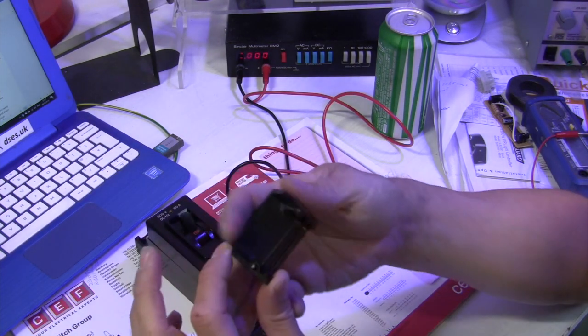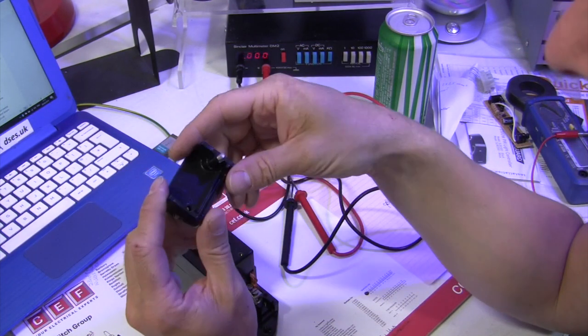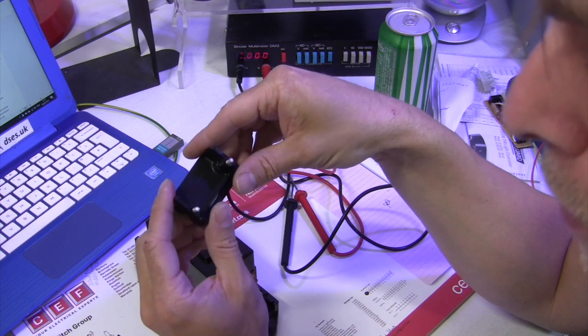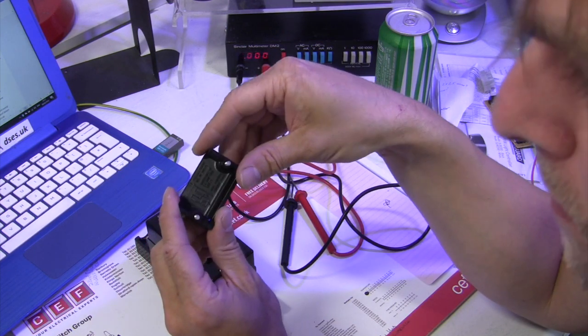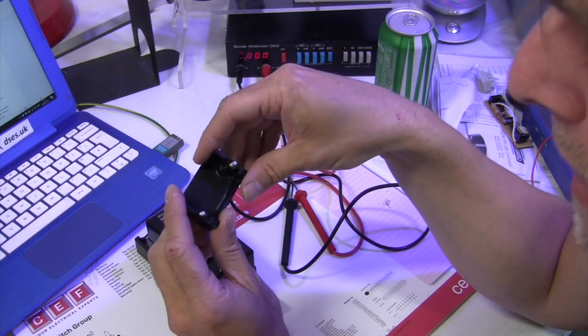And on the rear of the bottom cover, which I'm sure the camera is not going to pick up very well, but take my word for it. It states that the coil has an impedance of 500 ohms and that the maximum earth resistance of the rod must be under 500 ohms. It also says the minimum tripping current is 35 milliamps.